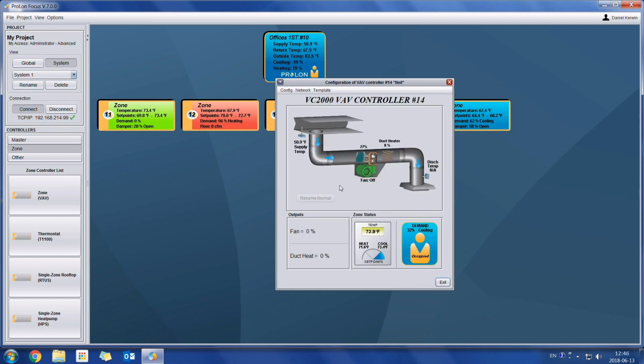Another feature on the Prolon Focus software is our template system. In the case where someone has a project with multiple VAV controllers, we can simply connect and configure one VAV controller, save its configuration as a template, and then reapply that template to all the other controllers. That way they will all be configured in exactly the same manner. So we're going to be saving a lot of configuration time by doing this.